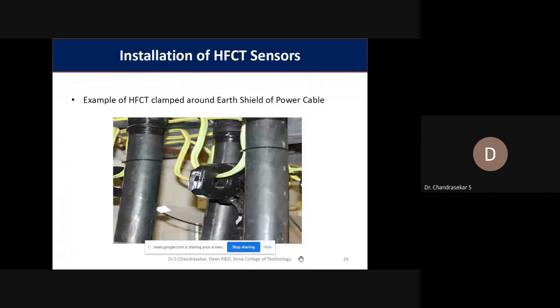Okay, so the main cable is there, the black portion, whereas the ground lead is the yellow colored portion. If you connect the sensor in the ground lead, then any leakage current or partial discharge occurring in the cable will flow through that metallic sheath, which is grounded. So we can easily get those signals through this HFCT sensor, and we can easily identify what is happening inside. Okay, if the level of the partial discharge or the leakage current exceeds the threshold limit, then we can immediately do the preventive maintenance work.